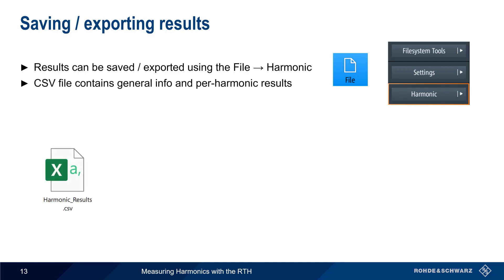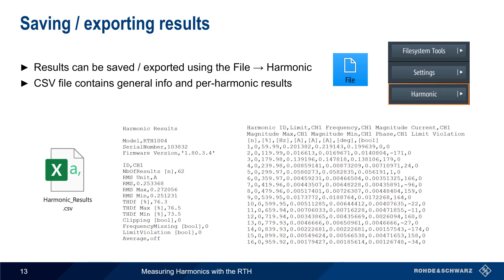In addition to providing a real-time display of the harmonics, the RTH can also save or export these values to a file using the File Harmonic menu items. The resulting CSV, or comma-separated value file, contains both general information about the instrument, settings, and overall measurement results, as well as detailed results for each individually measured harmonic. These results can be transferred from the RTH using either a USB drive, or over the RTH's Wi-Fi or LAN-based interfaces.